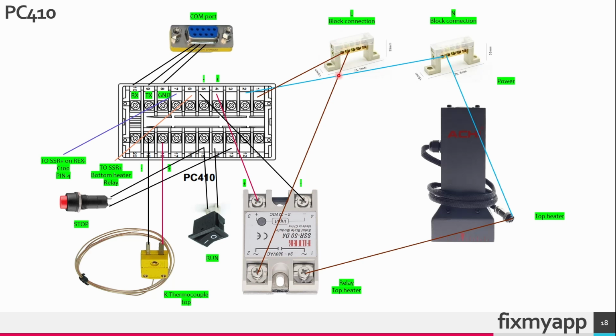The phase line will also go to number 2 of the solid state relay, and when this relay is turned on, the phase line will go to the output of 1, and then it will go to the top heater. The neutral line is directly connected also to the top heater. When this solid state relay is turned on, the switch is turned on, so the top heater will start generating the heat.